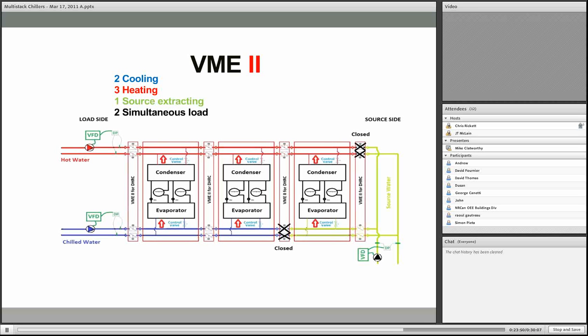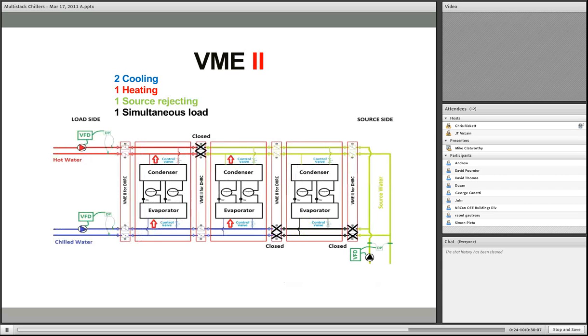And if there's not a weakness per se, but if there's one thing about this that requires extra thought, that is that in these examples, the fluid is all the same. So if you needed to provide an antifreeze, glycol, calcium chloride, Syltherm XLT, or something like that, if you needed that to be in the well field and you didn't want to run that into the building, then you would need an intermediate heat exchanger here. But that's certainly doable.